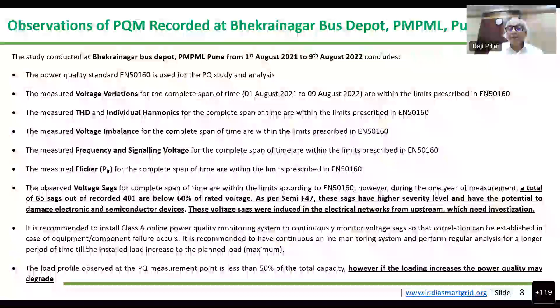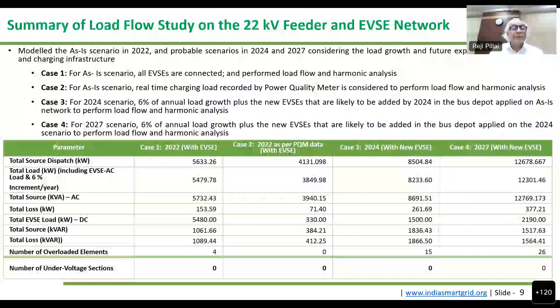And these are some of the scenarios which we studied with the model which we created, the load flow model. Case 1, As-Is scenario, all the EVSE is connected, and we performed the load flow analysis as of 2022. We also modeled the data based on a real-time recording captured by the power quality meter. That is in case 2. And for 2024 and 2027, we assumed higher charging loads, and we looked at the number of under voltage and overload elements.